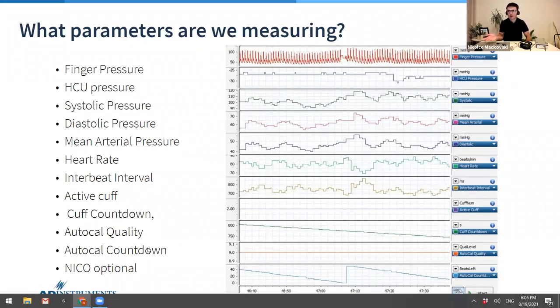The reason there is auto calibration is that this system requires, over time, to correct itself, because the theory behind this is to unload the artery. If you've never heard of that term before, that's okay. Basically, as we know, in systole the artery expands, and in diastole it constricts. The point of this is we want to have the diameter of the artery the same all the time. The way we can do that is by equaling the pressure in the cuff to the pressure within the actual artery itself. When the cuff pressure equals the pressure within the artery, the diameter stays the same. Therefore, the diameter will be unloaded. And as the pressure changes constantly within the cuff, this gives us a representation of what the actual mean arterial pressure is within the fingers.